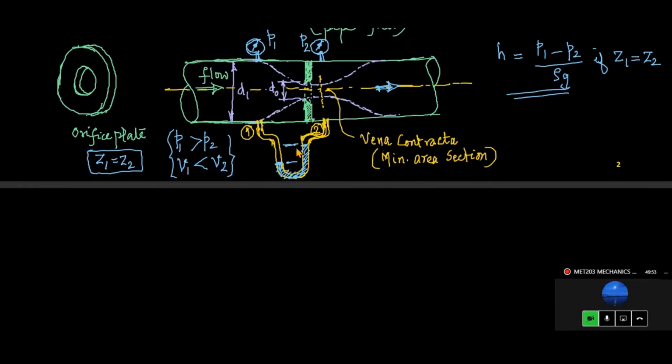So this reading, we will take the manometer reading, indicated as X. The basic formula is the same thing. H is equal to X into rho m by rho minus 1. Please understand, the unit of this is meters of flowing fluid through the pipe or the orifice meter.